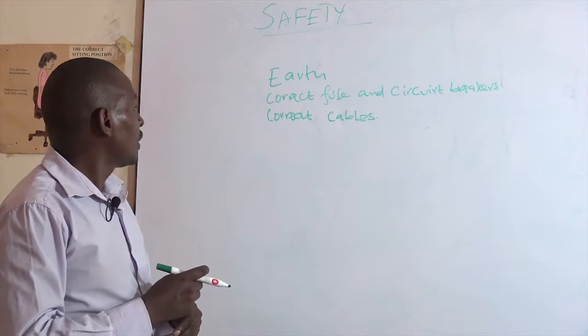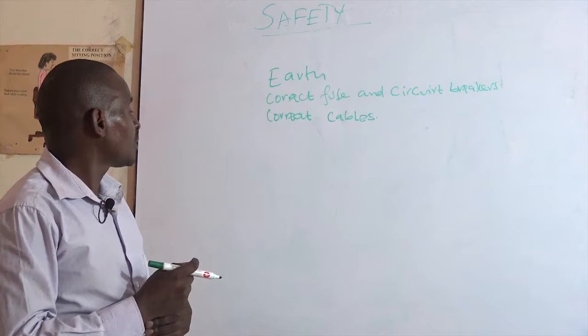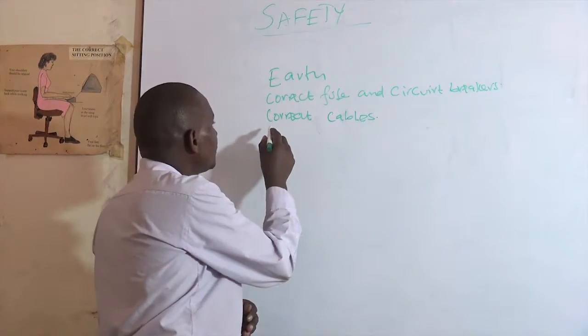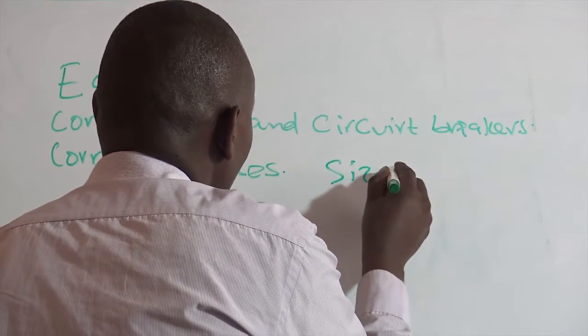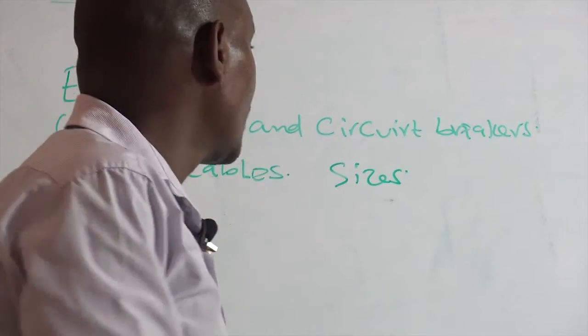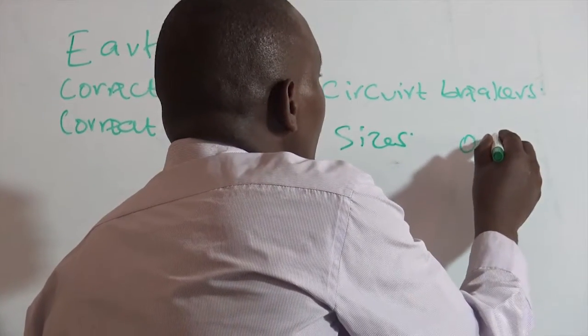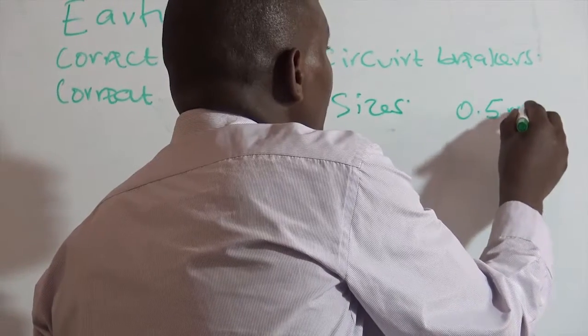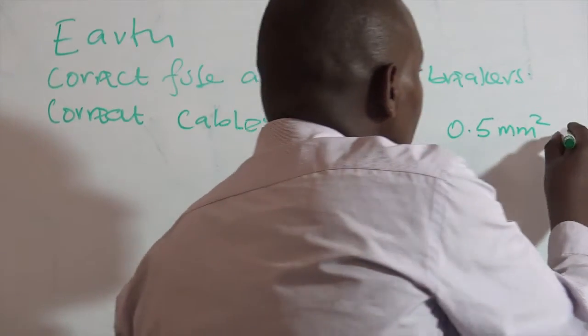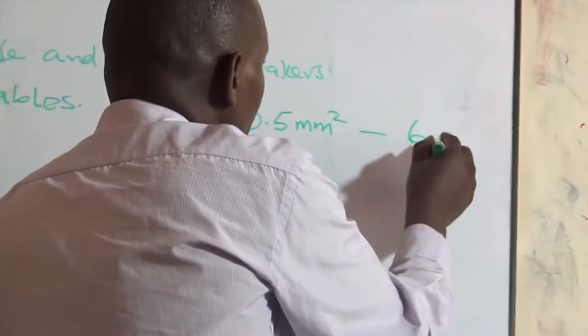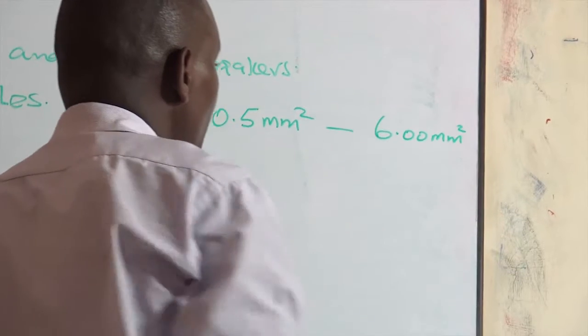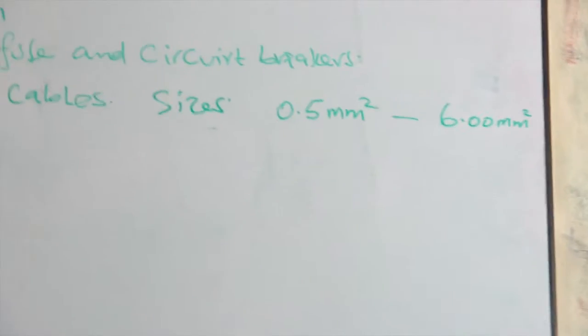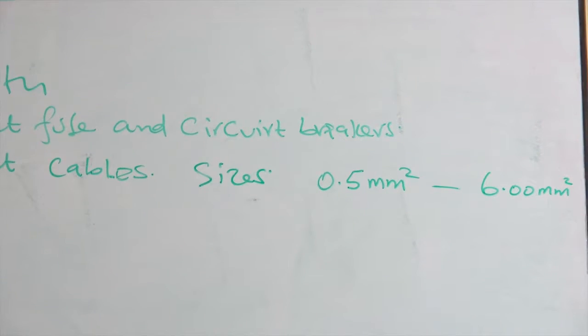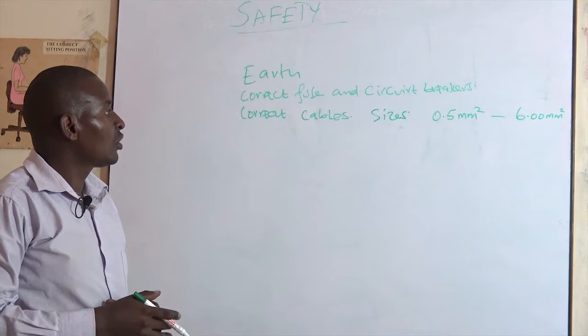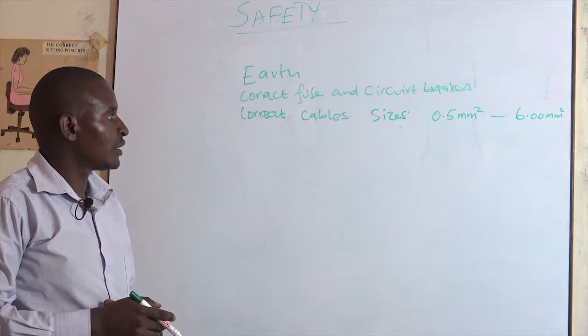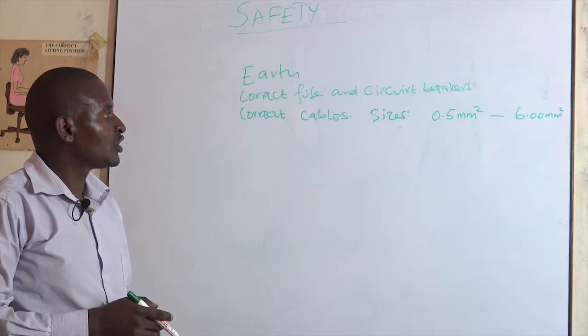This is because when you go to electrical installation, cables come in different sizes. We have sizes that are as low as 0.5 millimeter squared, and for domestic we go up to 6.0 millimeter squared. Now there is a reason as to why we have these cables and why they are rated as such.